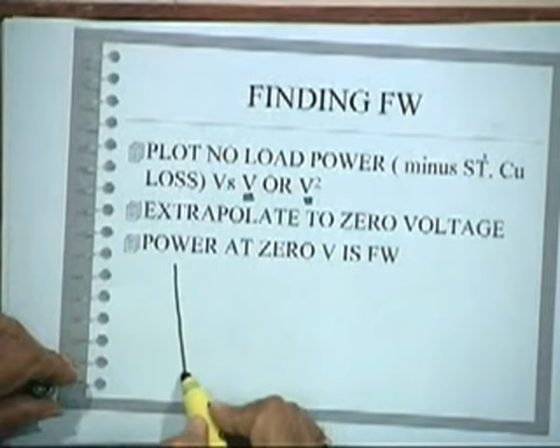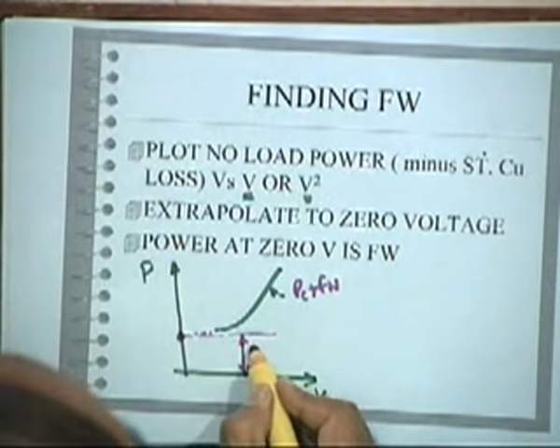Okay. And if you extrapolate it to 0 voltage, you got the result experimentally for different voltages, extrapolate to 0. What will it give you here? Because this is Pc plus friction windage, what you have measured. So at 0 voltage you expect core loss to be 0. So this will be the friction windage.